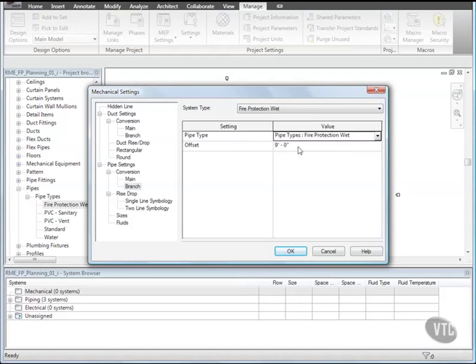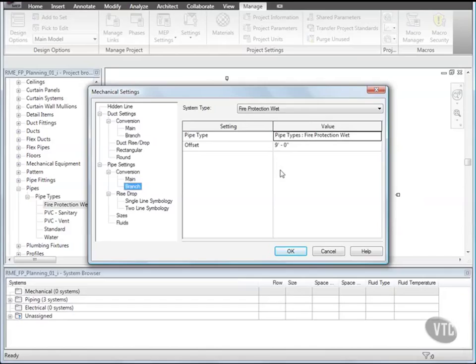The Offset Elevation for the Pipe Main places it at 9 feet above the referenced level for the views. Level 2 is the referenced level for the views where you'll be designing, so the Pipe Main will be offset from Level 2. Similarly, the Offset Elevation for the Pipe Branches places them at 9 feet above the referenced level for the views. The Branch Offset allows you to automatically create branches that run above or below the main and other obstacles.